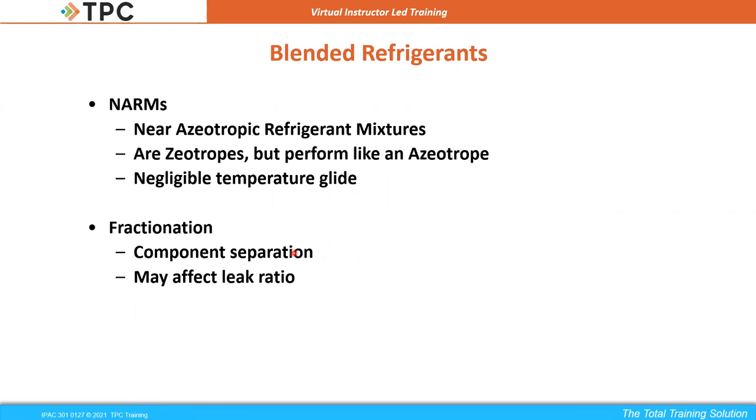When you're troubleshooting a system, if there's a leak with a blended refrigerant, you're going to leak out a percentage of the refrigerant, and you're not going to have the 100% blend you're looking for. So what you notice is that your superheat and subcooling are going to be way off. You check the system, you find a leak and you want to fix the leak. The best option is, instead of adding refrigerant to try to get it back up to the level where you want it to be, to take all that refrigerant out and weigh in the proper charge in a blended or a liquid method.